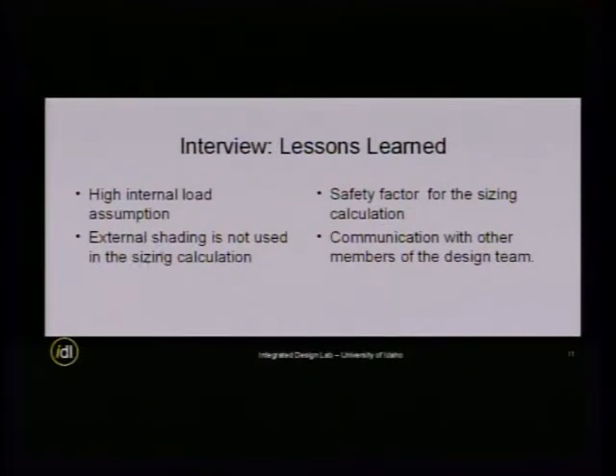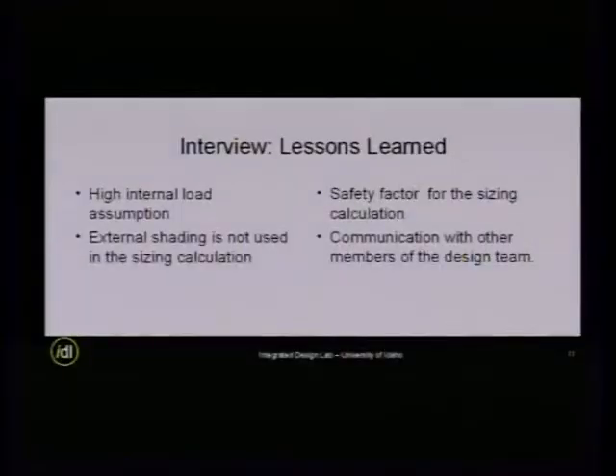And then the one thing that is so obvious is that external shading is never included in the calculation. It was just taken out of the building, even if the shading is fixed. So external shading, fixed shading, is never included in the calculation. For northwest orientation, probably it doesn't matter, nor for the north side, but for the south orientation, it will be significant. And then the safety factor, we'll talk about this more in a minute.